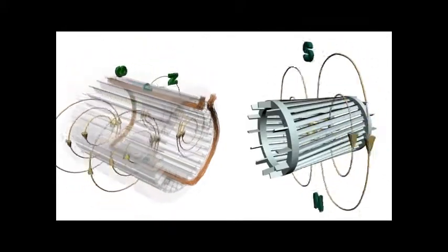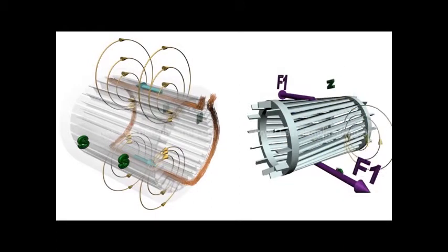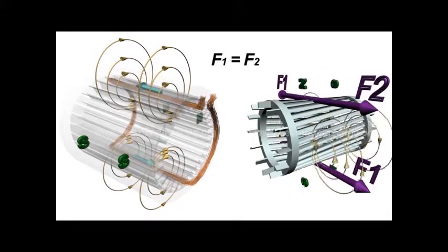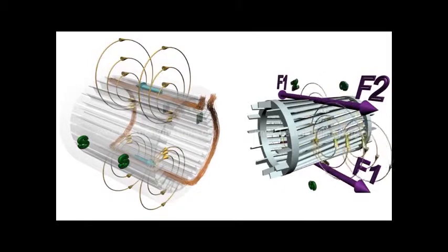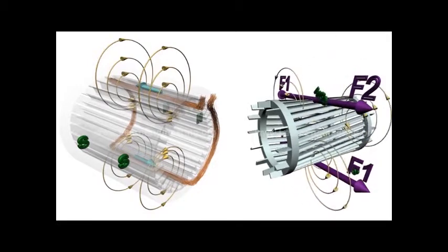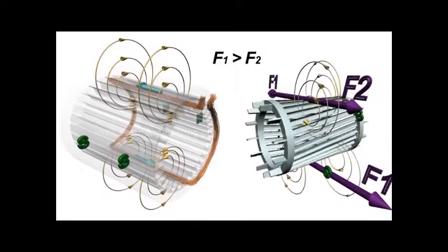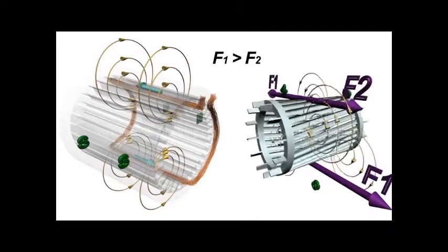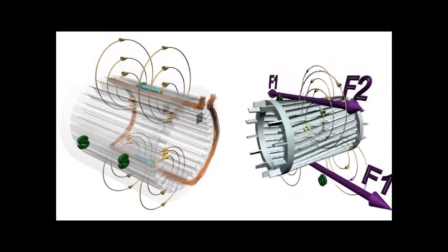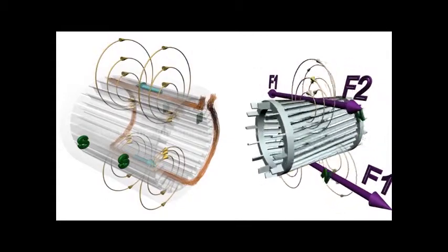The fluctuation induces current into the rotor bars that is surrounded by magnetic field, thus producing force according to Lorentz law. But there are two oppositely rotating magnetic fields, so torque will be both equal and opposite, and the rotor will have zero torque and will not start. It will simply buzz. We can overcome this by giving the rotor an initial rotation, so that one torque will be greater than the other, resulting in a net torque in the same direction as the initial direction. Thus, the loop will keep rotating in the same direction.